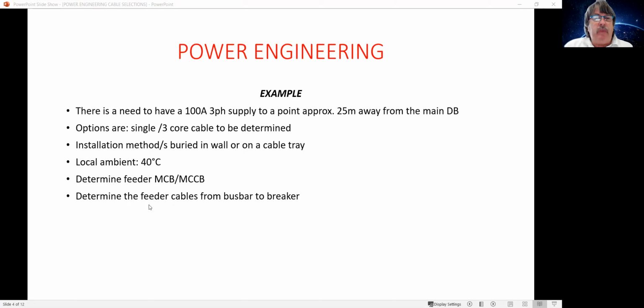So we're going to look at something like a typical example here so we can follow along. We're saying you need 100 amp three-phase power supply to something like 25 meters away from a main DB. The options obviously open at any one time are typically single core cables or a 3-core cable, to be determined really in this little mini session that we can go through here.